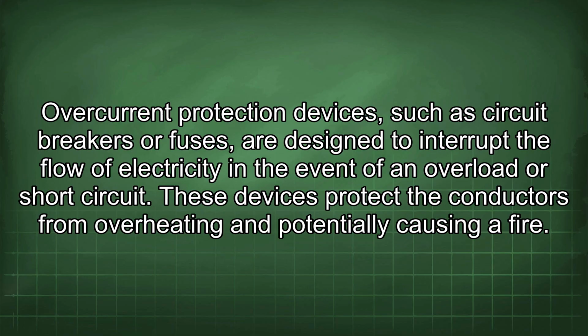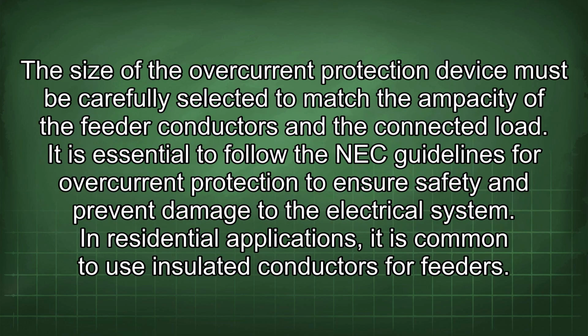Overcurrent protection is also required for feeders and subpanels. Overcurrent protection devices, such as circuit breakers or fuses, are designed to interrupt the flow of electricity in the event of an overload or short circuit. These devices protect the conductors from overheating and potentially causing a fire. The size of the overcurrent protection device must be carefully selected to match the ampacity of the feeder conductors and the connected load.